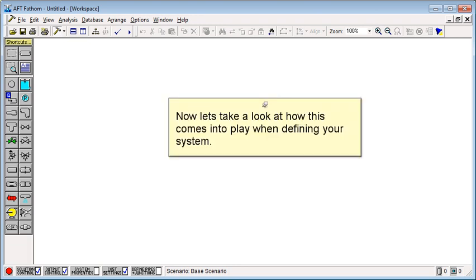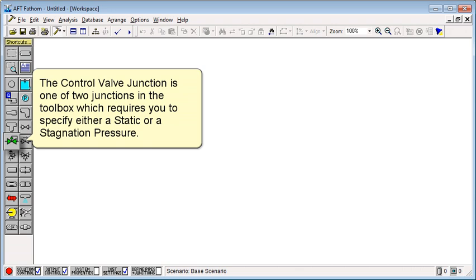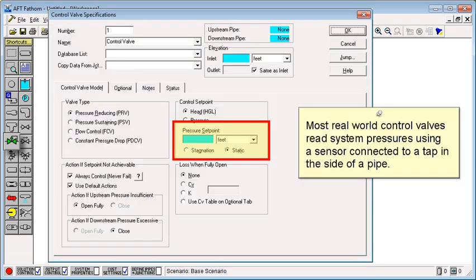Now let's take a look at how this comes into play when defining your system. The control valve junction is one of two junctions in the toolbox which requires you to specify either a static or a stagnation pressure. Most real world control valves read system pressures using a sensor connected to a tap in the side of a pipe.